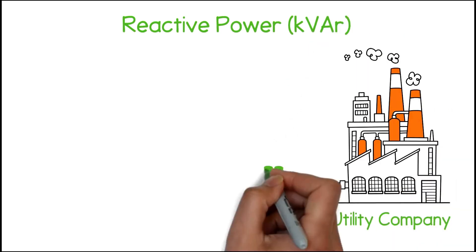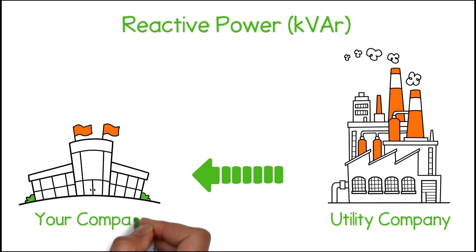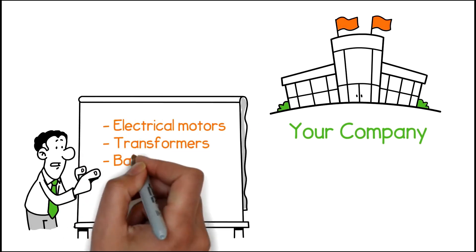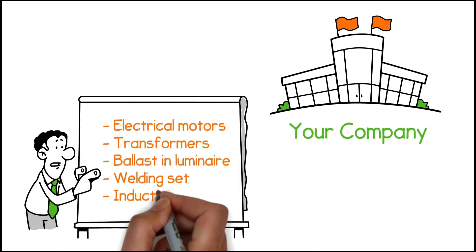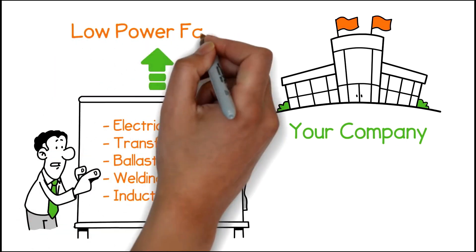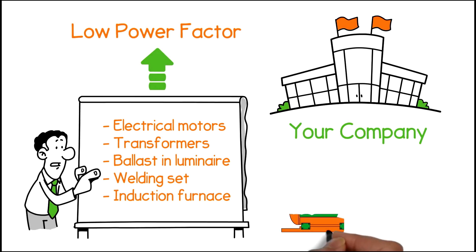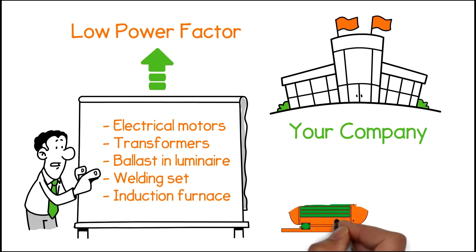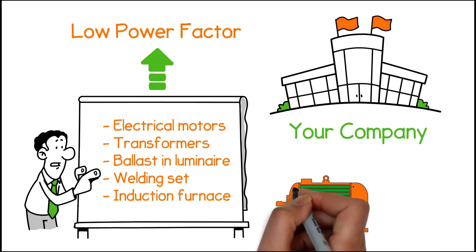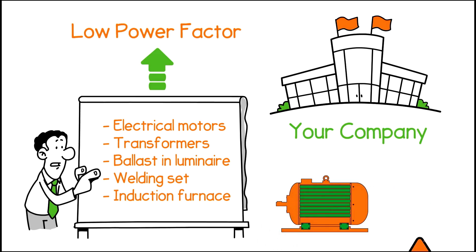Reactive power is the non-working power delivered to a facility. Why would you have non-working power? Inductive power equipment such as electrical motors, transformers, a ballast in a luminaire, a welding set, or an induction furnace are just some of the equipment that will cause your facility to run with a low power factor. Nearly every site, no matter what your industry, will have a poor power factor. And if you have a KVA demand component on your bill, you will be penalized for having a poor power factor.